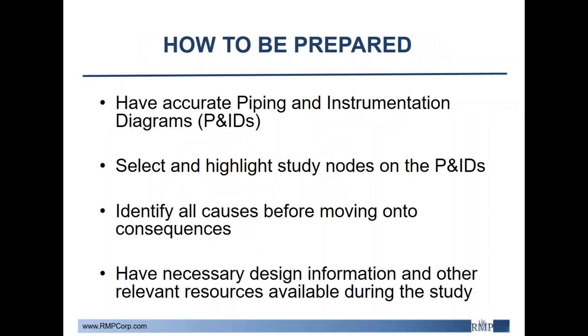Moving on to how to be prepared. Knowing the kinds of things that will be discussed during a HAZOP makes for a more organized and efficient study. This saves time and improves the quality of the product, since session time can be spent brainstorming scenarios more unique to the facility, such as non-routine situations like startup and shutdown. The best way to prepare is to first have accurate piping and instrumentation diagrams, or P&IDs. Inaccurate P&IDs can lead to inaccurate HAZOPs, as a majority of the study will be spent referencing these drawings.